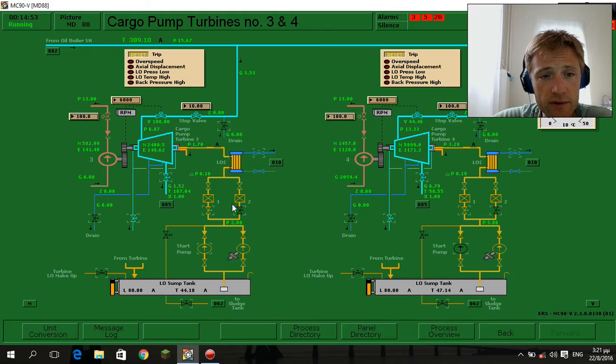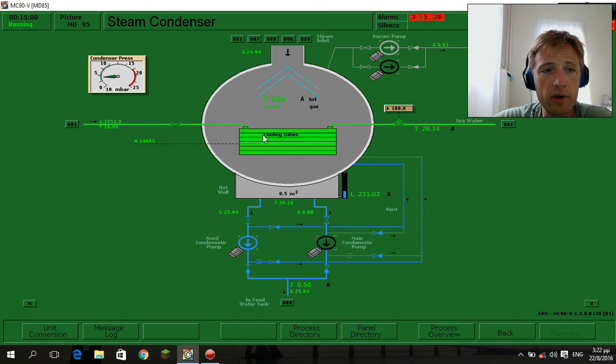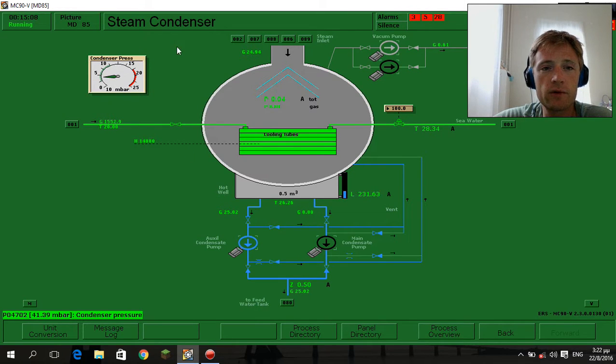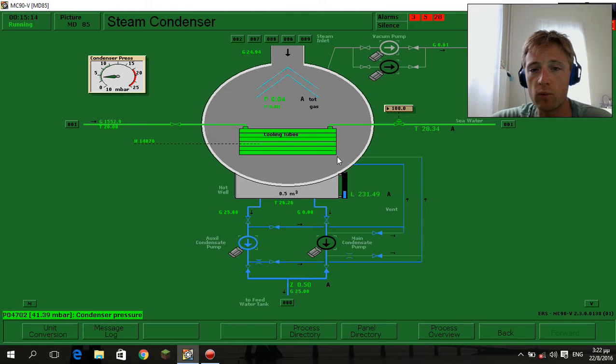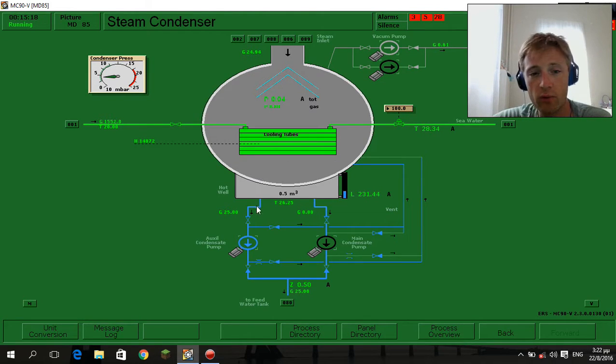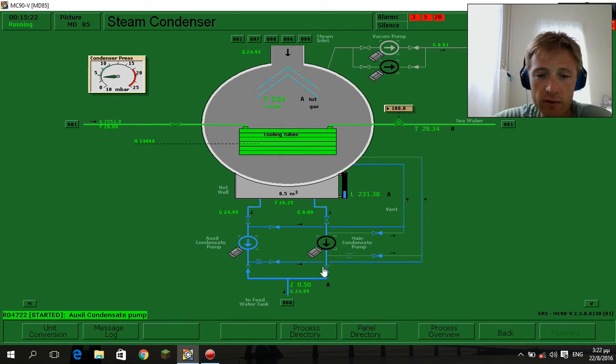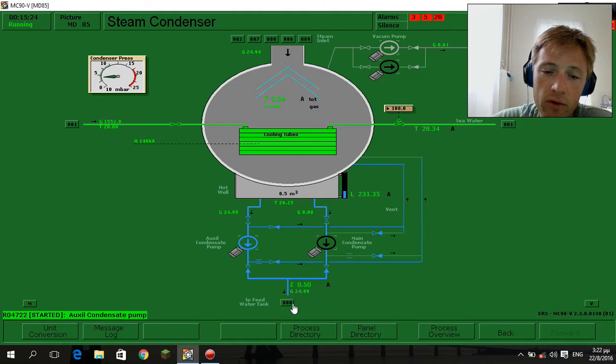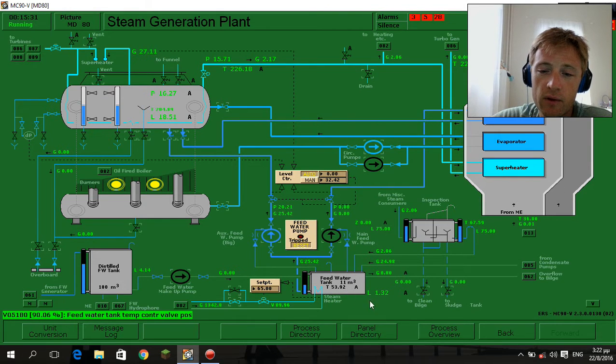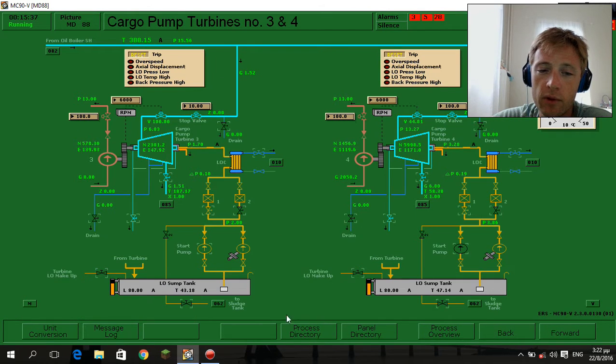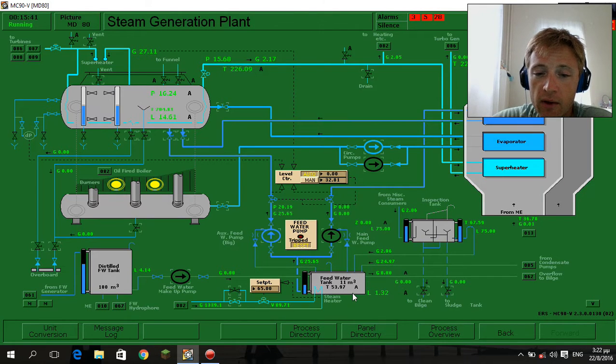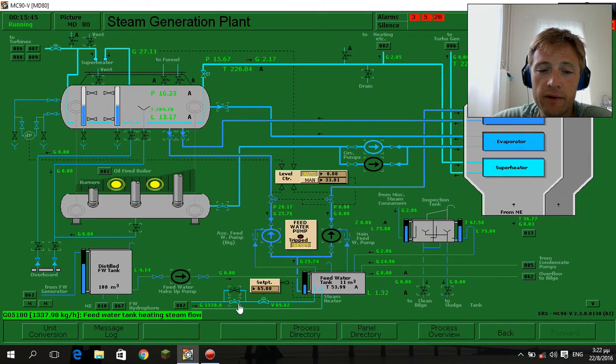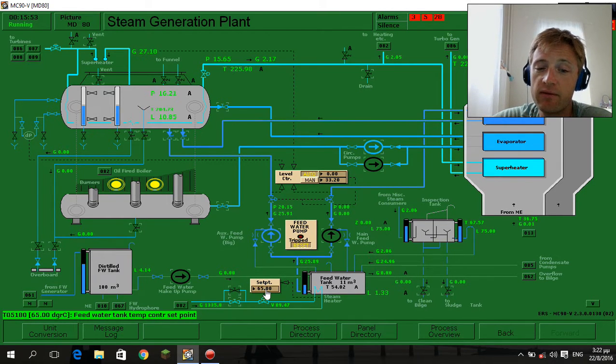Next we will go to our condenser, and very important - the vacuum must be proper. As you can see here, our condenser pressure vacuum is okay, it's in the green zone. So our steam will condense here and cool to transform to water. In this part will remain only water which will be sucked by the condensate pumps and will be sent to the feed water tank. The feed water tank, which is here, will send this - the feed water tank, as you can see here, has steam tracing steam heater. So to keep as you can see here 65 degrees.